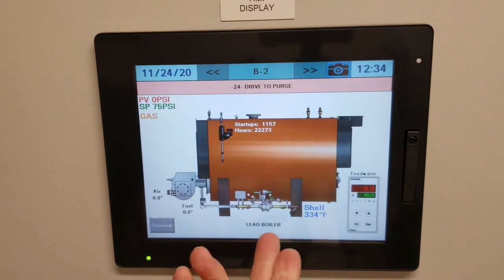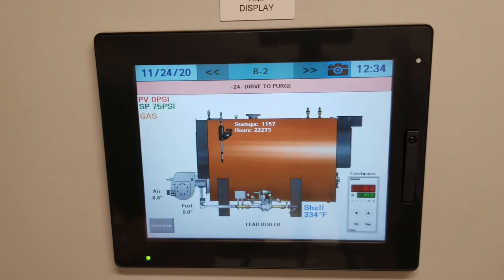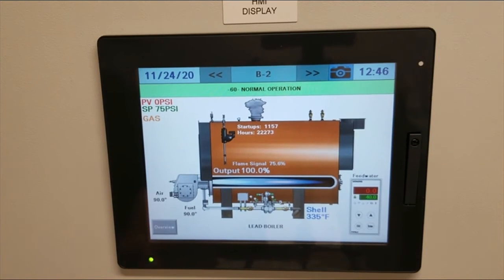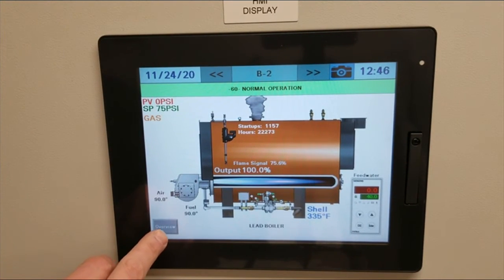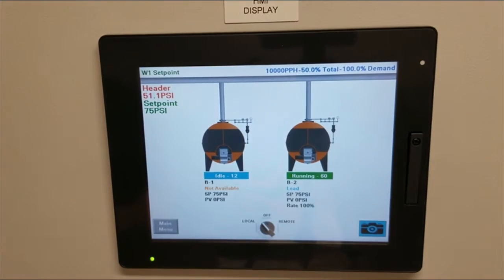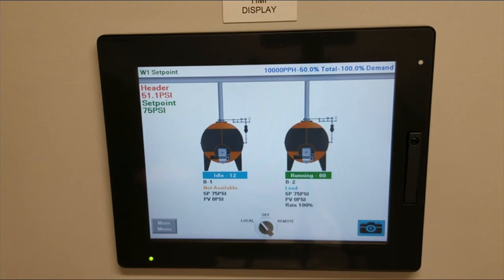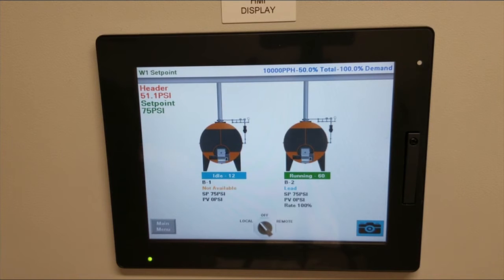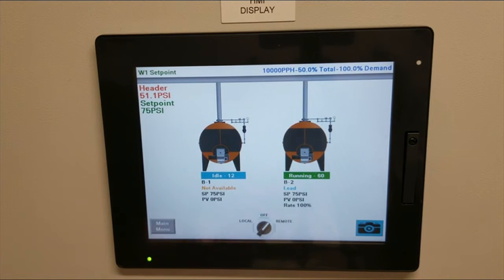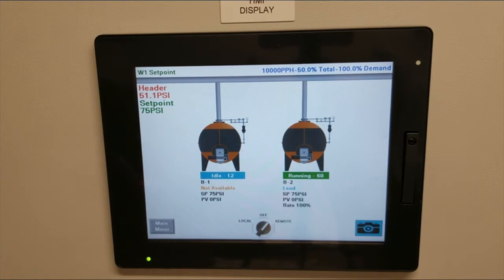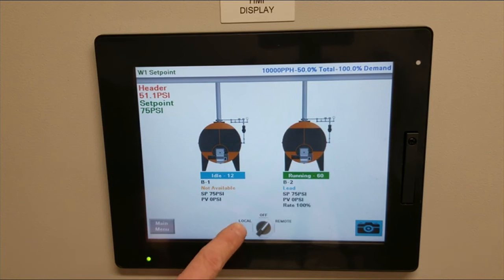Click on the boiler and you'll notice it now shows as the lead boiler and the burner is starting. Now that the burner is running, go to the bottom left-hand corner Overview tab and click it. This takes you back to the main screen. One thing to note: at the bottom you'll see a button that says Local, Off, or Remote. If the set point or firing rate is coming from the master panel, leave this on Local Control. If you're getting a set point from a building management system, press and hold Remote — the master panel will receive its set point remotely and modulate the burners. In our example we do not have a BMS, so we set this to Local Control.